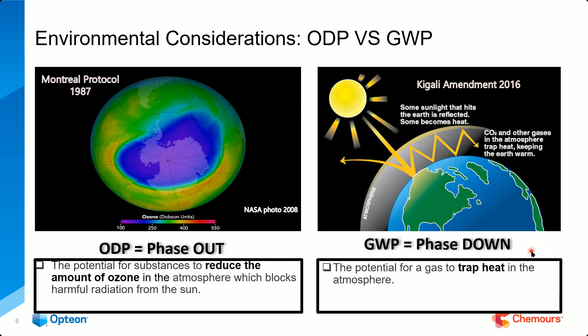So this is the reason they're trying to find, or they found, refrigerants that have a lower GWP, which simply means they break up faster in the atmosphere. And that's what the goal is. This is not a phase out. In some areas, it's pretty aggressive, but it's a phase down. Eventually, we will buy reclaimed refrigerant with our HFCs, just like we do R22 today. But we're moving to a lower GWP refrigerant, and we have a bunch of items to talk about today.